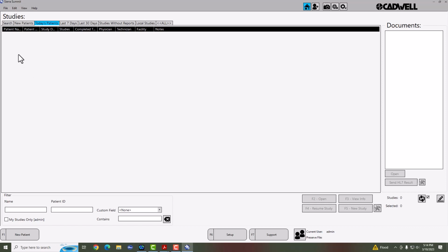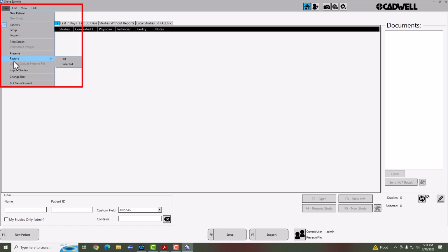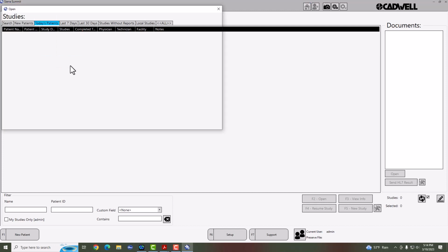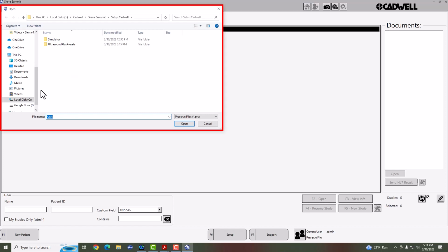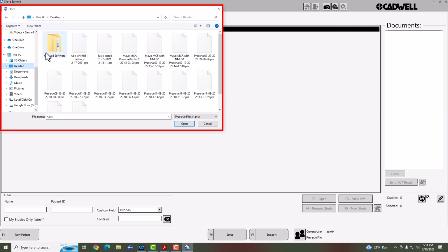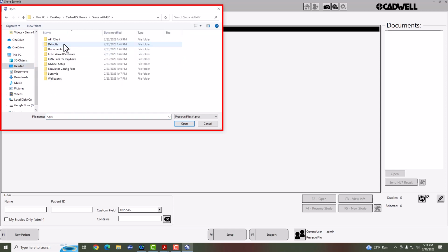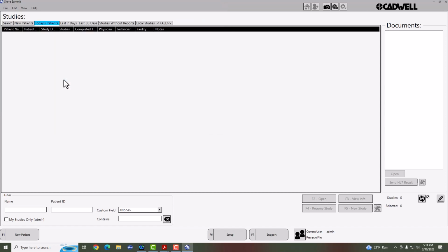So to do that, we're going to go to File, Restore Selected. We're only using Restore Selected because we only want to bring in that one protocol. We don't want to restore any other settings from the default preserve file. Then we're going to browse to the default settings for Sierra 4.0. Those should be found in the install media, wherever you've kept that. And they're under the defaults folder. Double click on the Sierra 4.0 defaults.